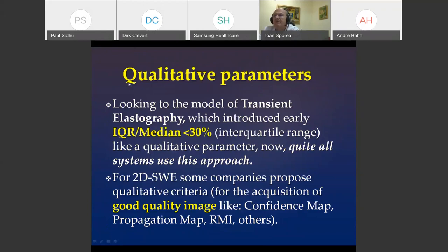Qualitative parameters are very important for evaluation in elastography. Transient elastography was the first to introduce IQR/median — interquartile range over median — which must be below 30, and this is now used by all machines as a quality parameter. For 2D shear wave elastography, many companies propose supplementary qualitative parameters such as the confidence map, propagation map, RMI, or others to ensure good image quality.